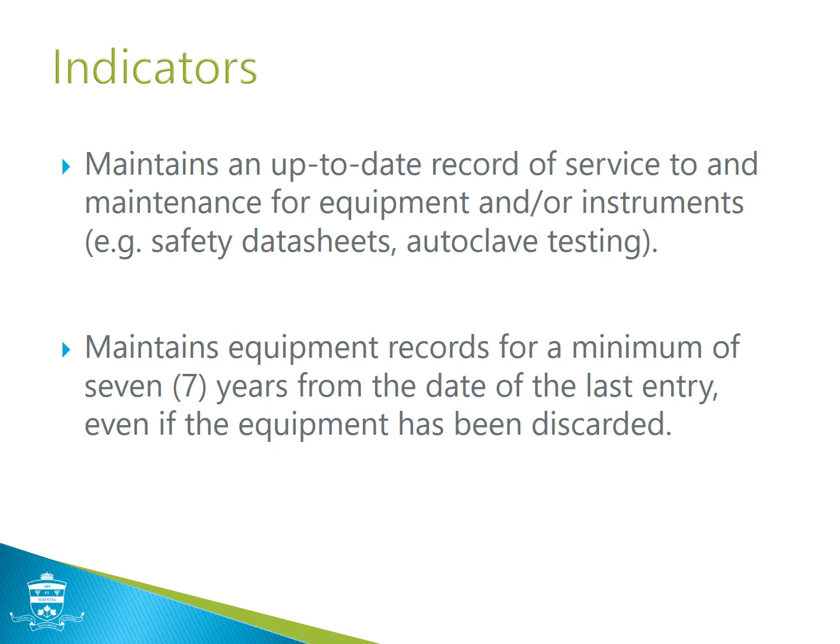Some indicators for this standard statement include maintaining an up-to-date record for service to and maintenance for equipment and/or instruments, for example, safety data sheets, autoclave testing, spore testing logs. Another one would be maintaining equipment records for a minimum of 7 years from the date of the last entry, even if the equipment has been discarded.